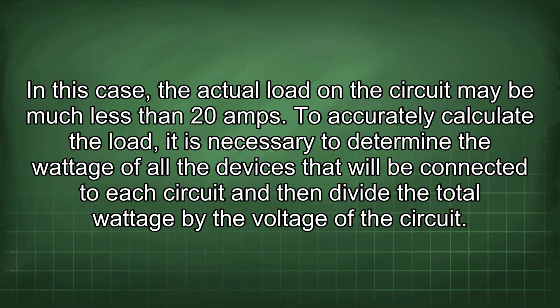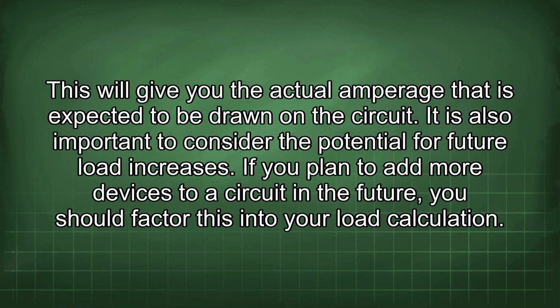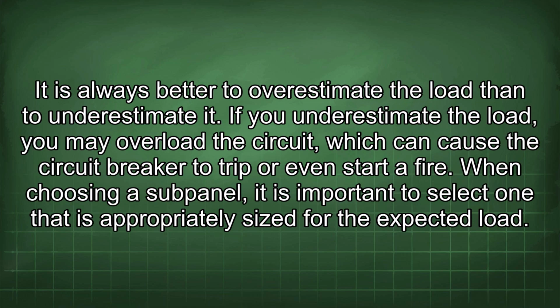To accurately calculate the load, it is necessary to determine the wattage of all the devices that will be connected to each circuit and then divide the total wattage by the voltage of the circuit. This will give you the actual amperage that is expected to be drawn on the circuit. It is also important to consider the potential for future load increases. If you plan to add more devices to a circuit in the future, you should factor this into your load calculation. It is always better to overestimate the load than to underestimate it.